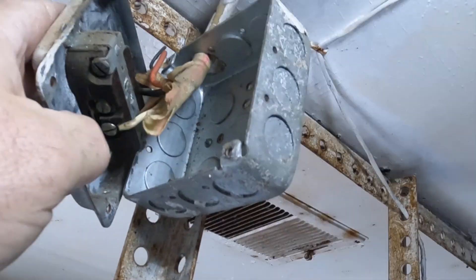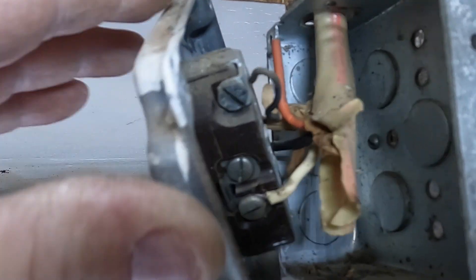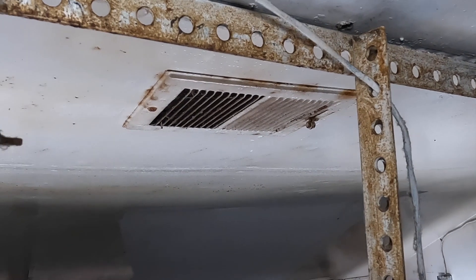I don't think the ground was even connected. Oh, here's the ground — but it looks like it fell off, came disattached. It was here. See, because it would reach right there — that's how I know that it came apart. No big deal, right? So this whole thing then had a problem: no longer grounded, no longer bonded to the system, and could become energized.